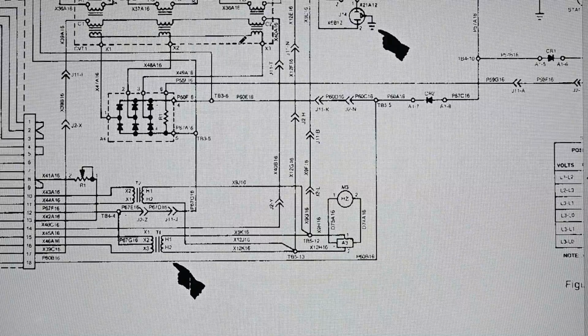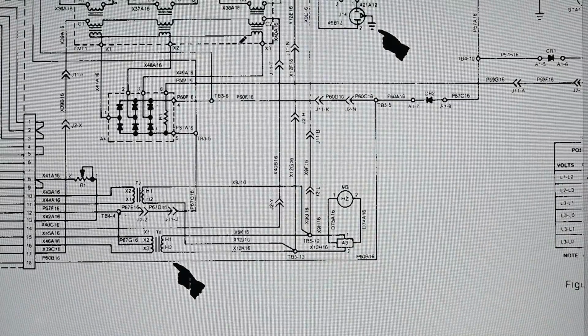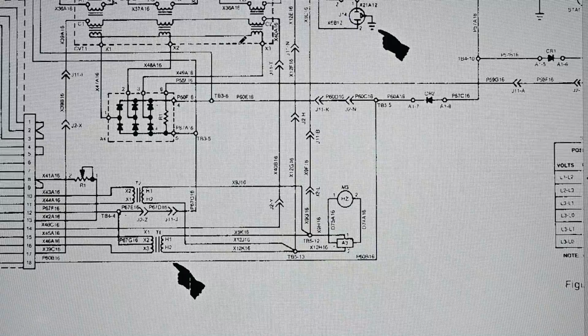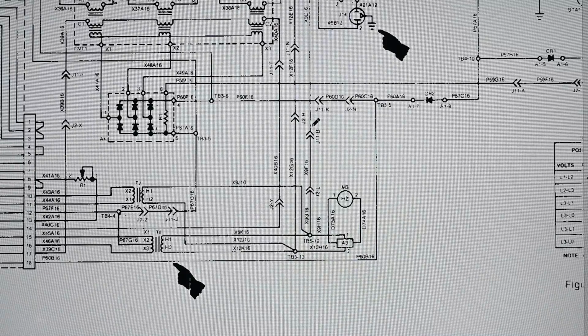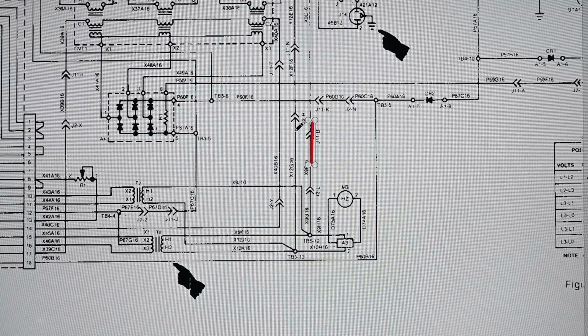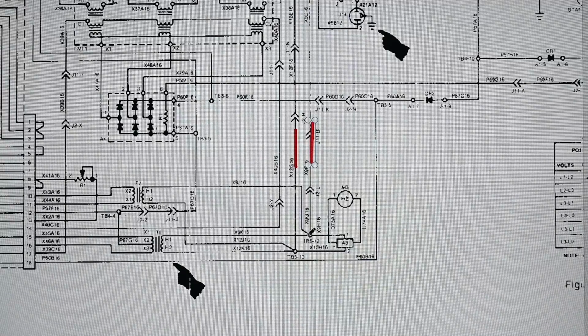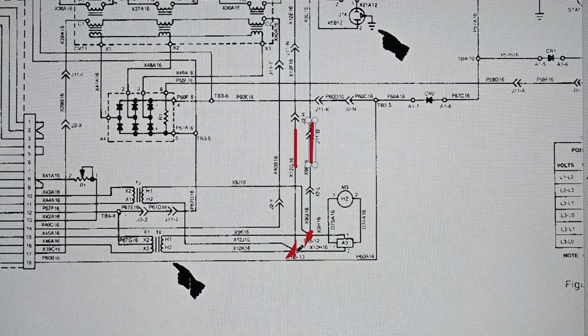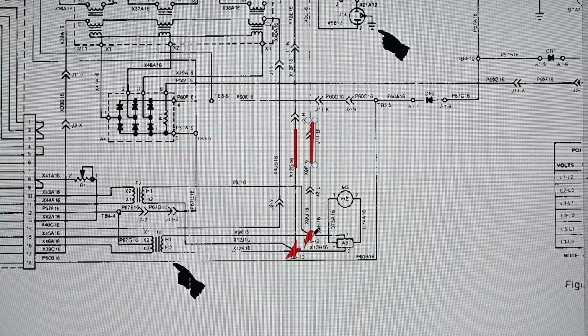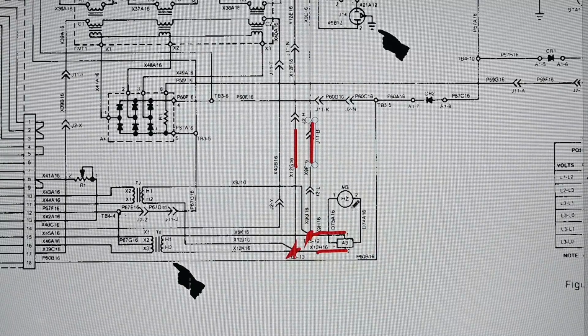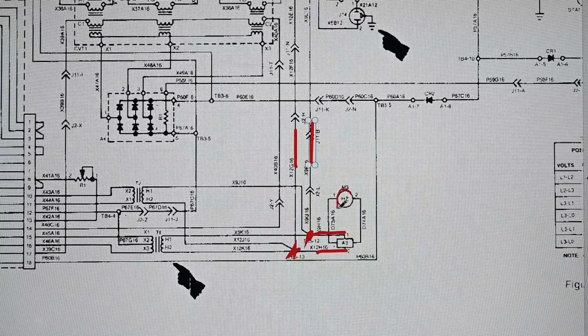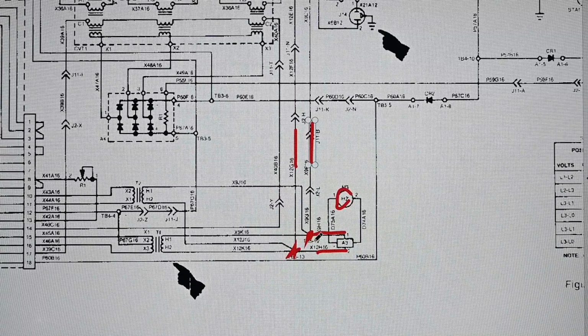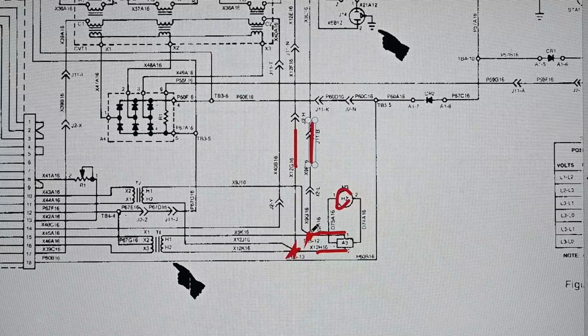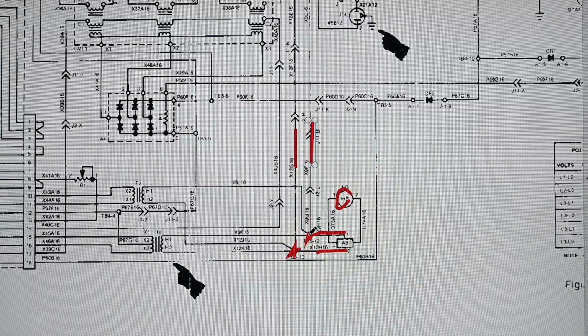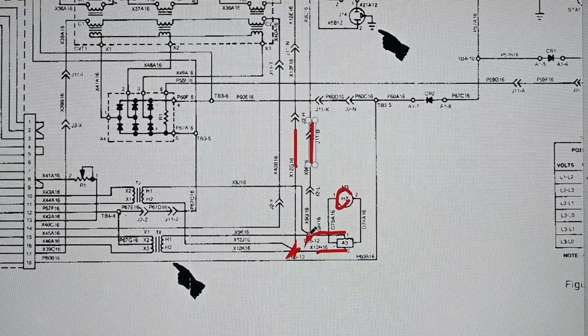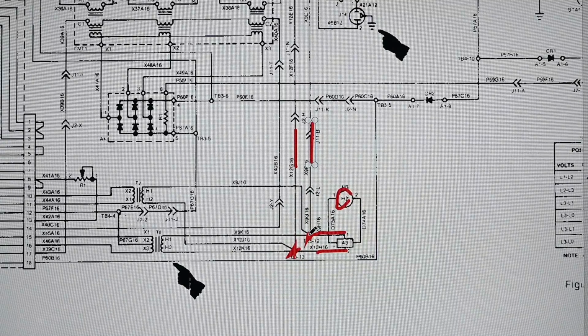As long as the generator is producing voltage, no matter how the AC reconnection switch is set up, there will always be about 120 volts on these two wires. They come down to this terminal board here and here, in the control panel. On one side it comes over to the frequency converter and the frequency meter or hertz meter, so that has nothing to do with voltage regulation. But again, there's always 120 volts on those wires, or very close to it. As the generator is starting up, that voltage rises up to that value, and when the regulator takes over, it'll be very close to 120 volts.